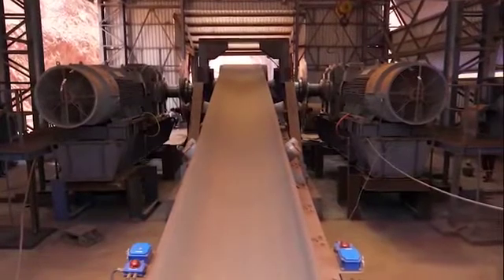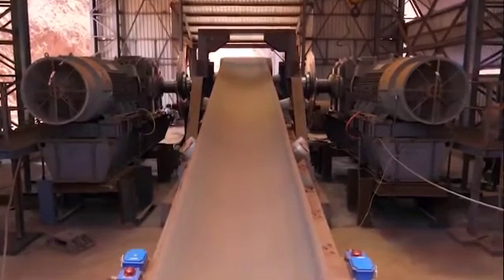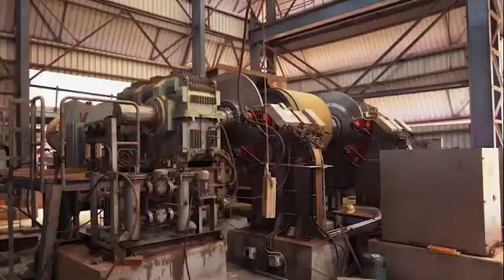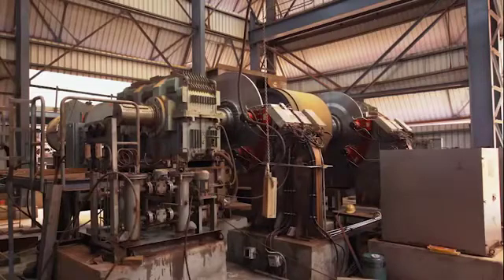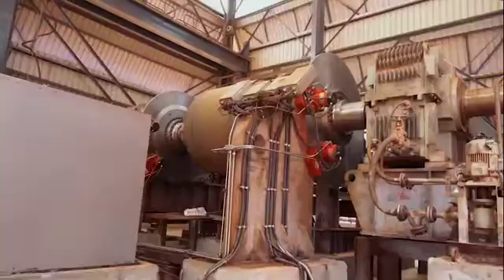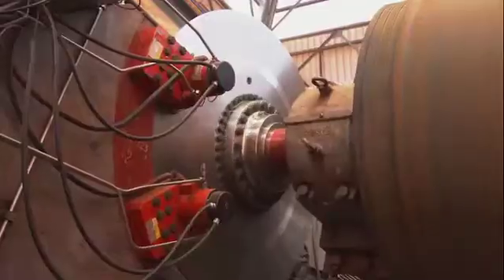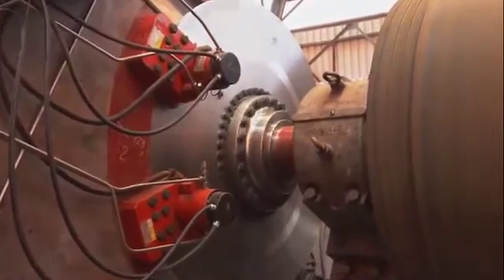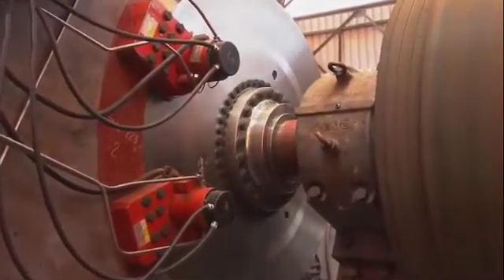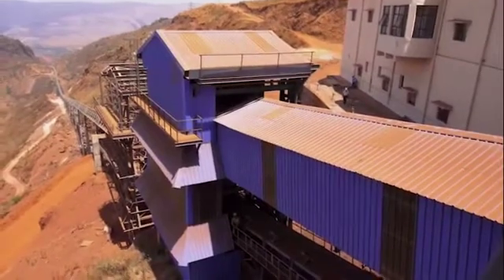This conveyor has two variable frequency drives, VFDs, at feeding end and has a total capacity of 800 kilowatt times 2, which means 1.6 megawatts motor power, designed for both positive as well as negative mode of operations, and during regeneration, generated power is then fed back into the network. Also, one of the most advanced, both proportional and digital controlled disc braking systems is installed to ensure this conveyor is 100% secure and fail-safe in the event of an unforeseen calamity, power failures and emergencies.